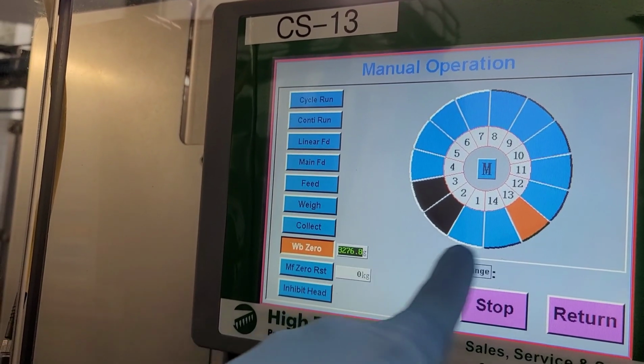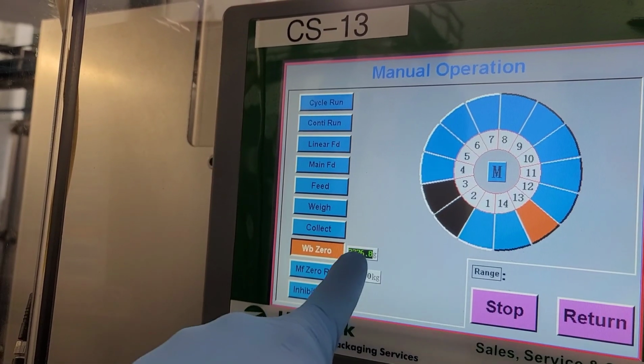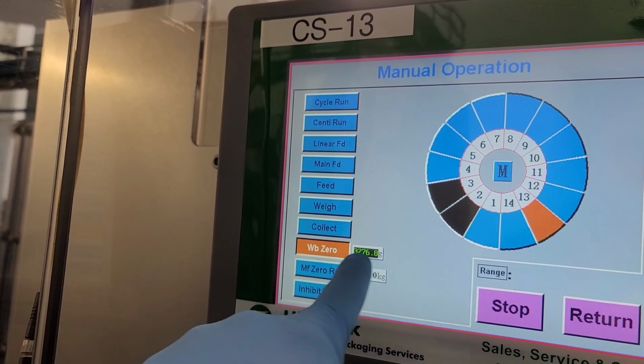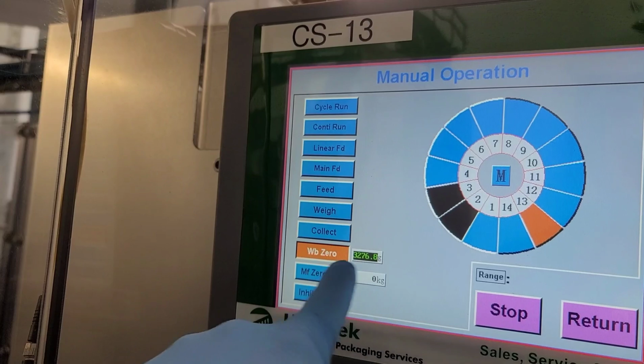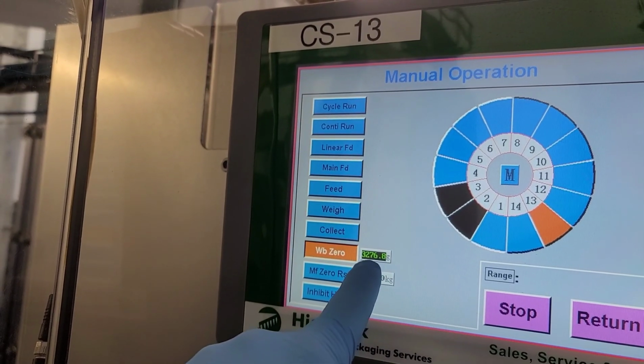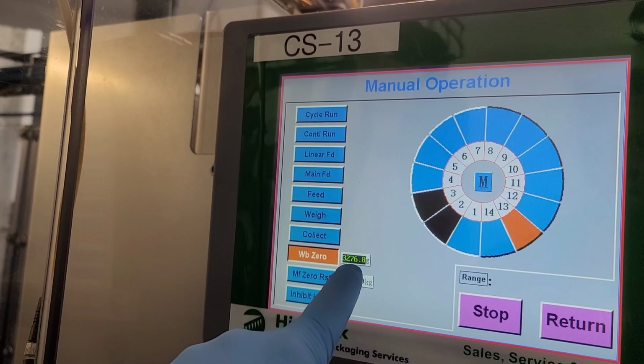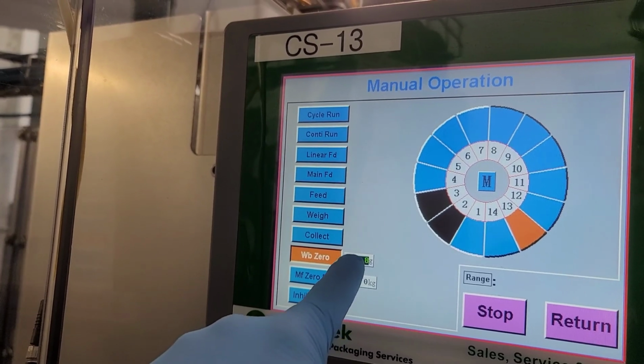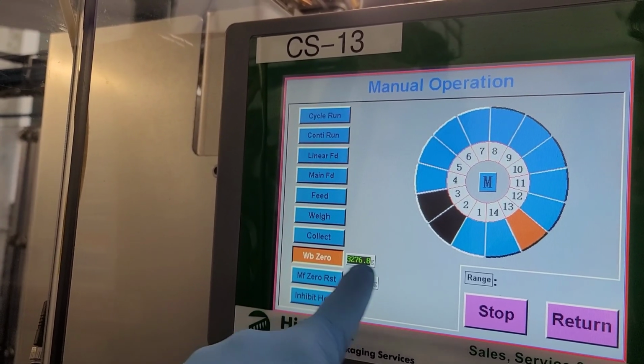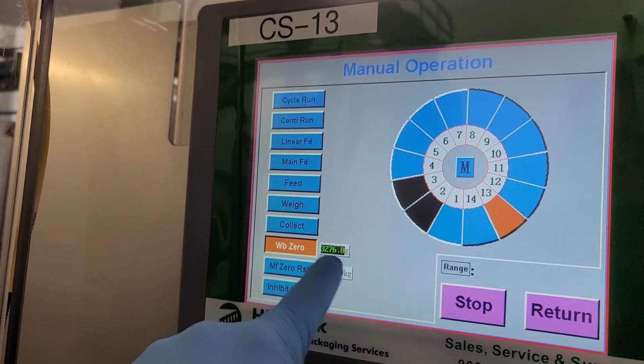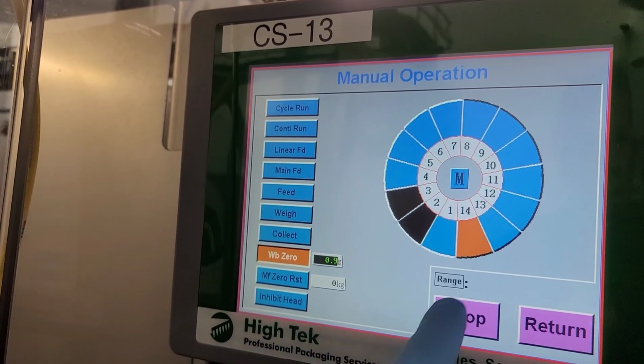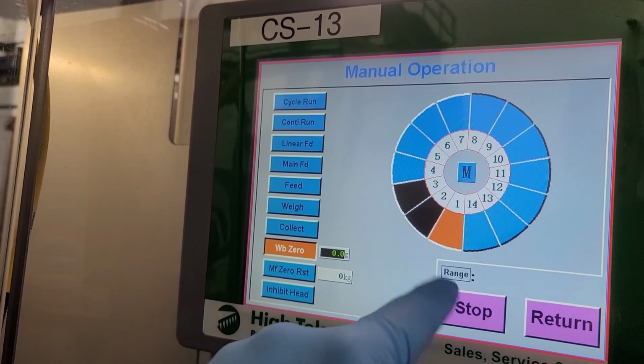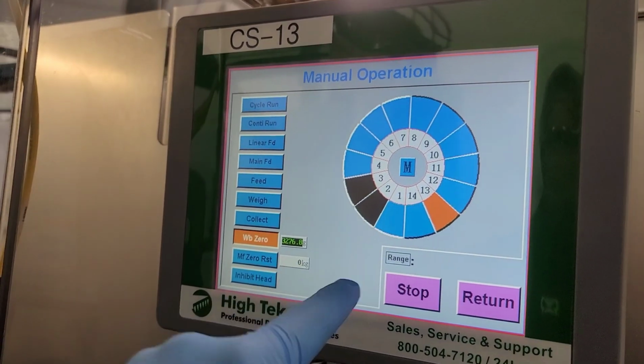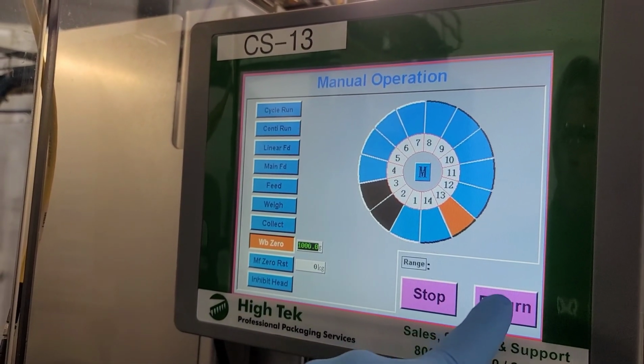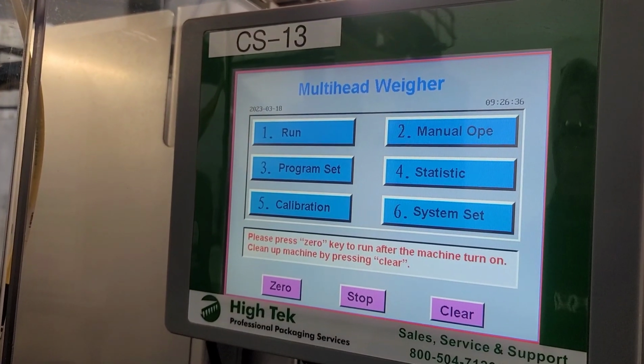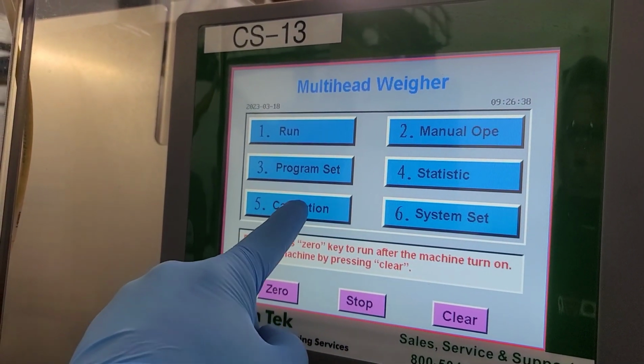Oh, except for here. We've identified a bucket that is having an error. This number is common when a bucket is overweight or out of calibration, and you will see that number appear exactly like this on other buckets as they have errors. 14 is good, and back to 1. We're good. So we have identified 13 as the issue. So we are going to return to the main menu and enter the calibration menu.